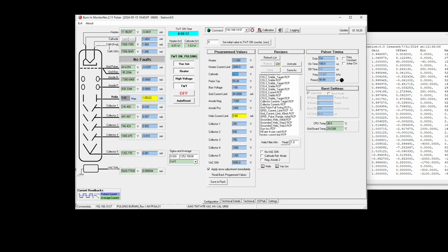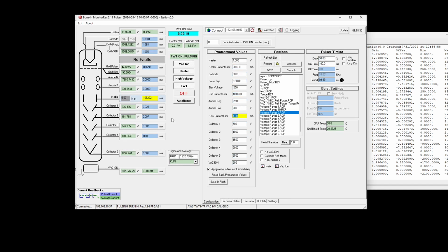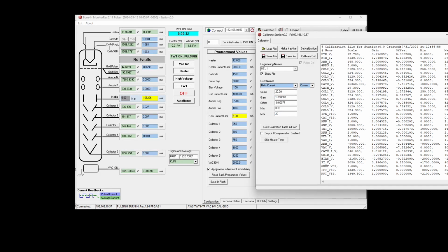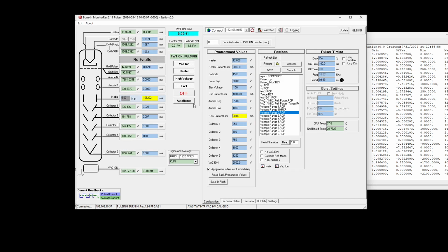Now what we can start to do, I've got a set of recipes here that will slowly step up this voltage. We also want to take our Helix current limit, trip level, up to maximum. Let's also double check. We need to make sure that our maximum is also at 20 milliamps, same as our scale. We're going to take this up to 20. Recipes always overwrite that, so I'm just going to manually type in 20 after I load the recipe. I double click voltage range 2. This sets it to 3000, and I activate.